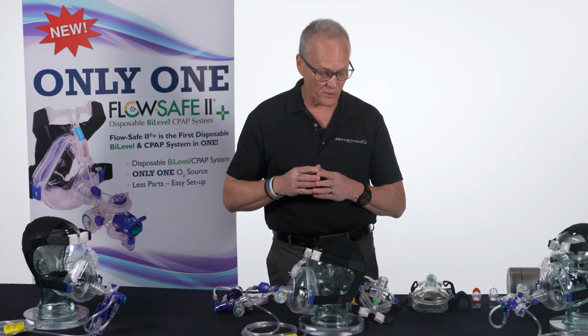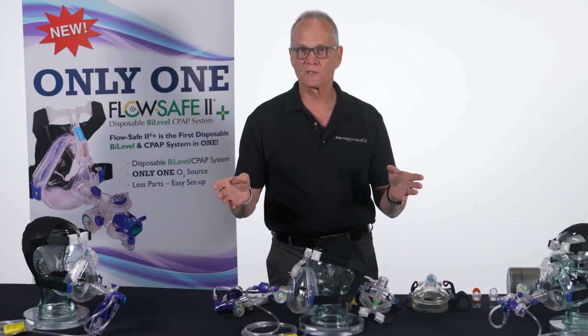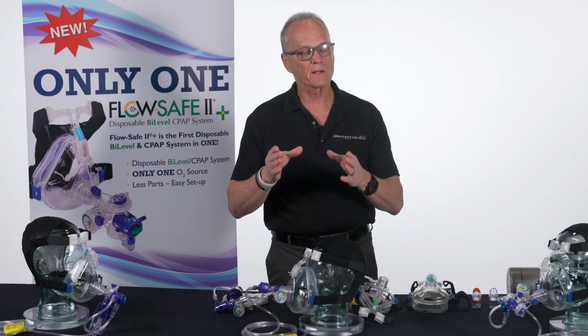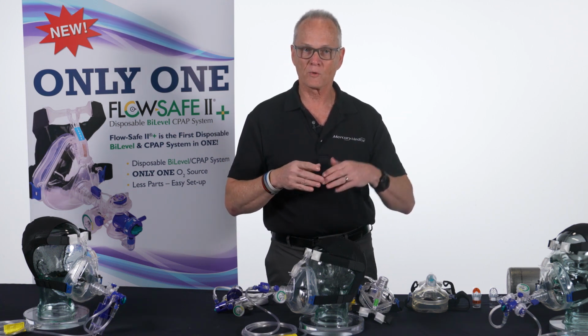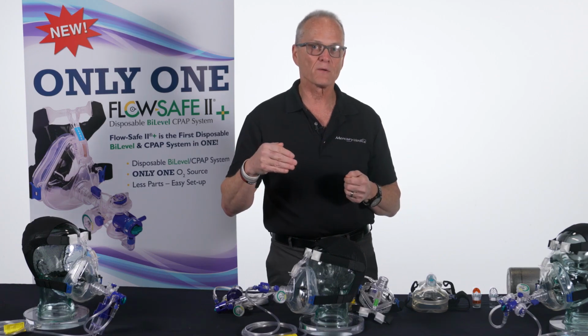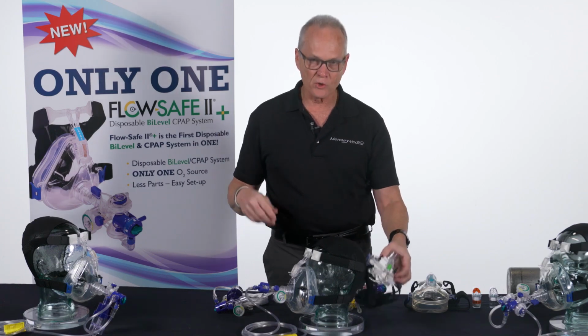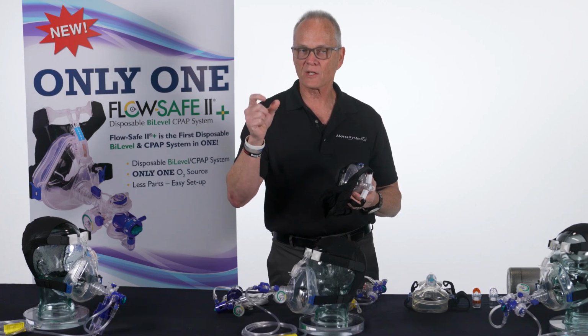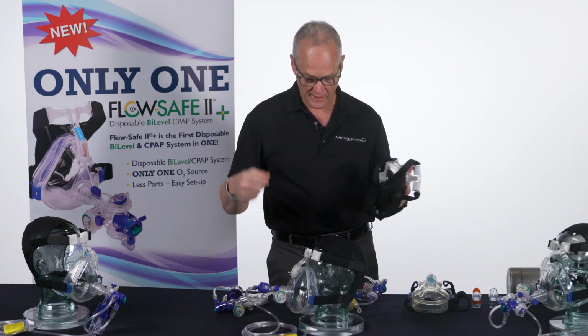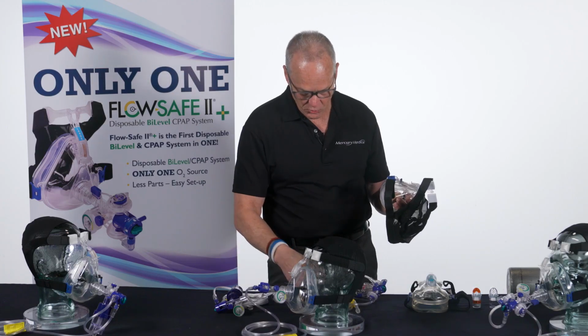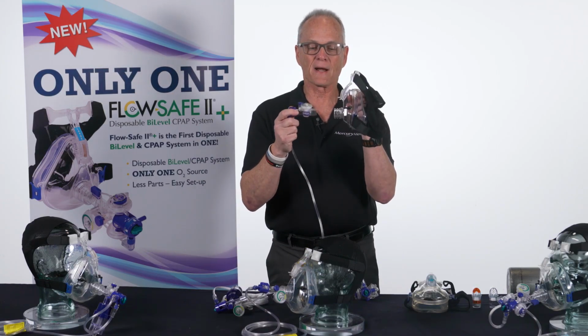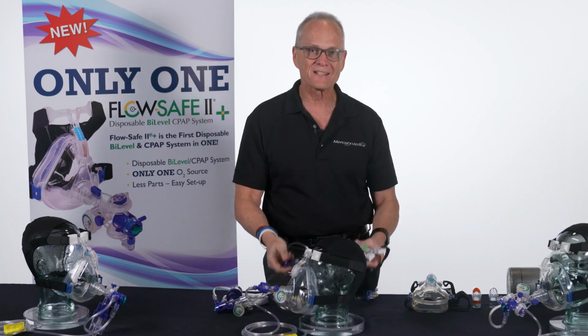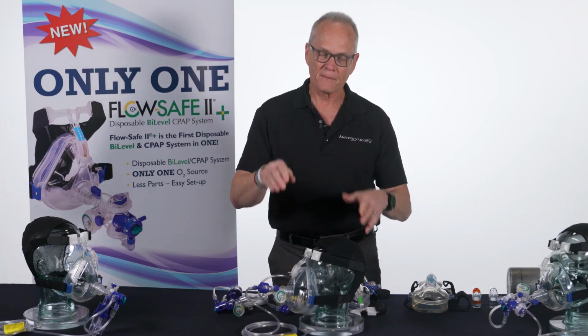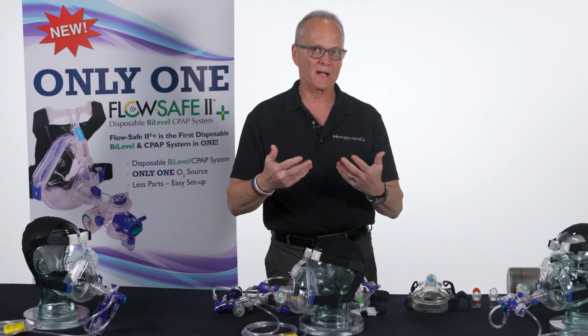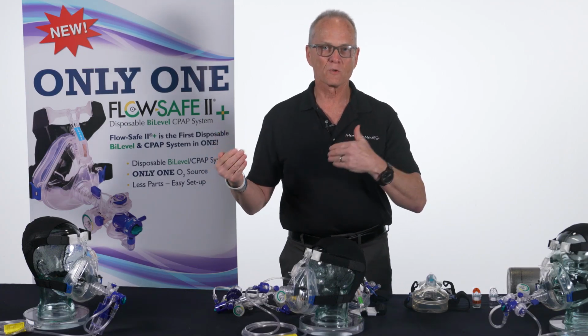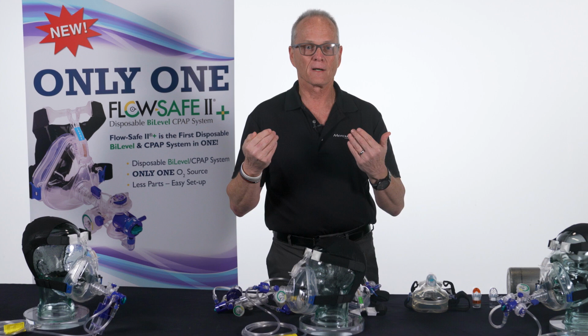Now, I just mentioned end-tidal CO2. For all of the FlowSafe devices, there's two ways you could try to measure end-tidal CO2, whether you want to do capnometry, which is a number, or capnography, which is a graph. If you tried to use the connector for end-tidal CO2 that goes on an endotracheal tube, it will actually fit between the FlowSafe valve and the mask. It would fit in between the two. But I can tell you that's not very effective. The gas flow going through the valve is so fast, it washes the CO2 out, so therefore your graph is not going to be of any value.